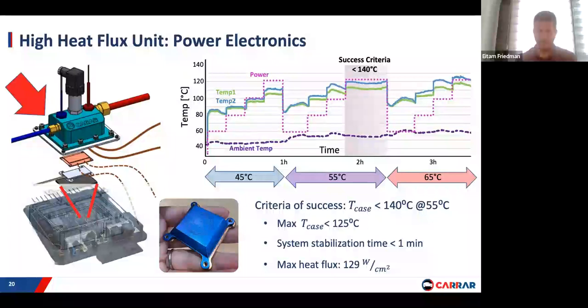You can see the green and blue lines, which are the two temperature measurements, very close to each other. The dotted purple line is the power, and the ambient temperature is the purple line below. You can see that when we reach maximum power, we were around 125 degrees at 55 degrees ambient, which is a huge success.